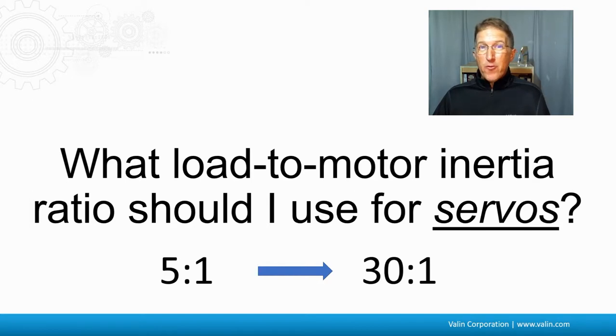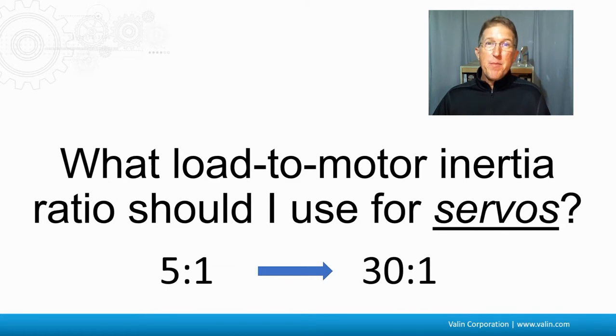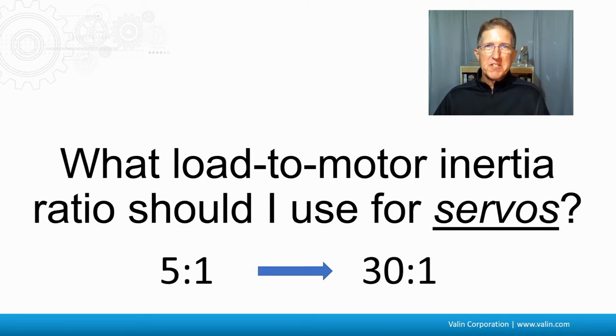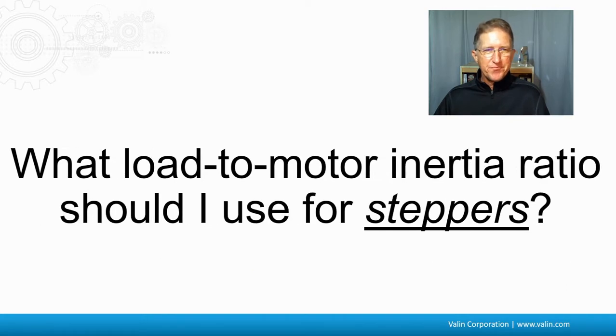What's the problem with going over those ratios? It becomes very difficult — or even impossible — to tune, and the system may become unstable. So if you find yourself unable to tune your servo system, check your inertia ratio and see if you're just way out of range.